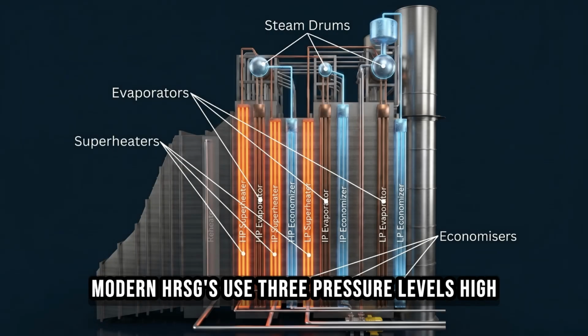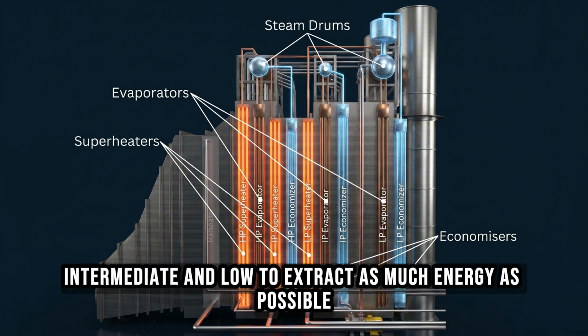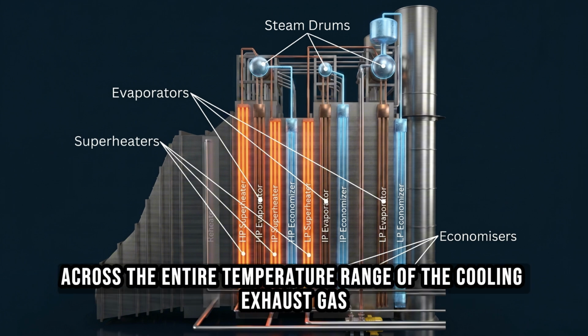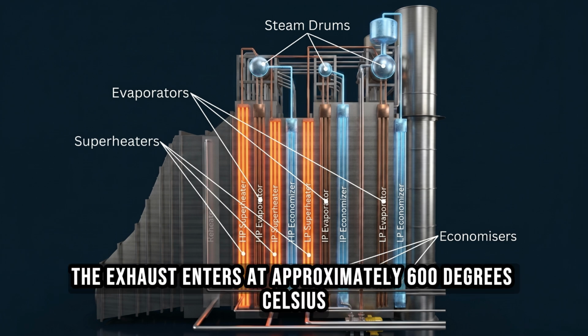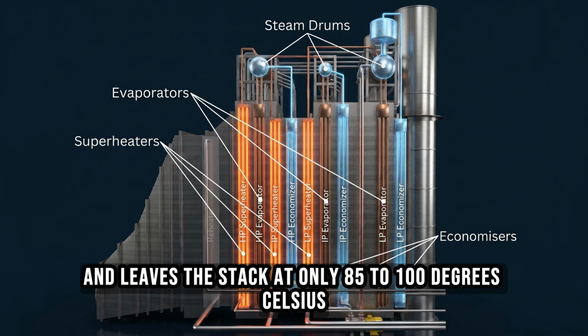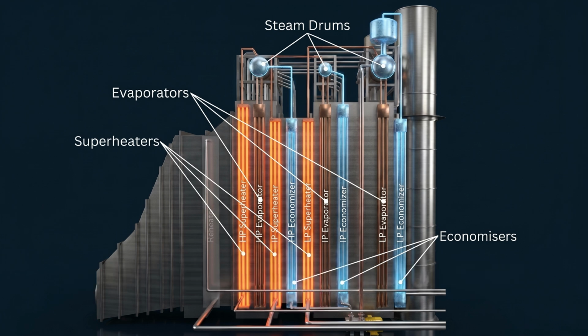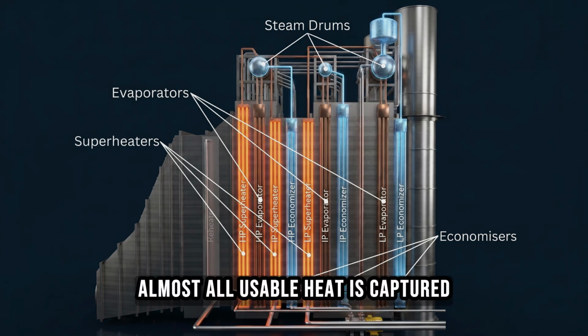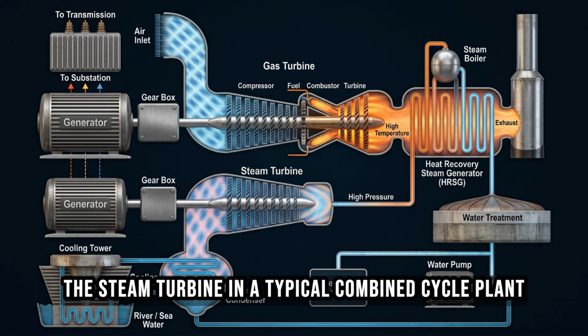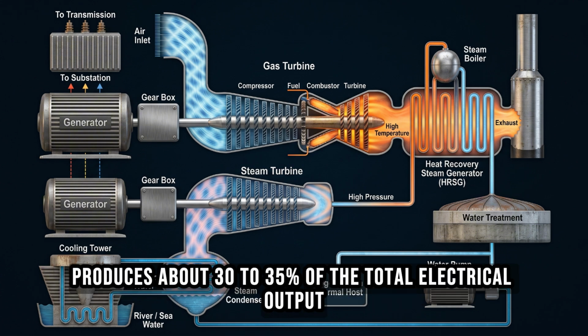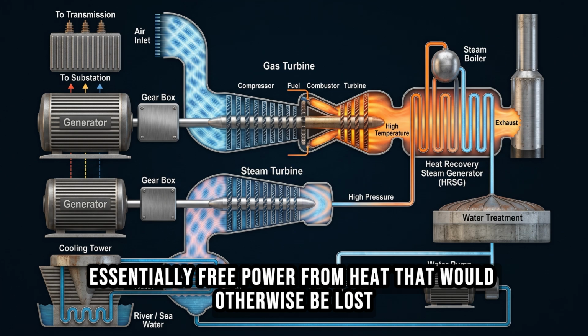Modern HRSGs use 3 pressure levels, high, intermediate, and low, to extract as much energy as possible across the entire temperature range of the cooling exhaust gas. The exhaust enters at approximately 600 degrees Celsius and leaves the stack at only 85 to 100 degrees Celsius. Almost all usable heat is captured. The steam turbine in a typical combined cycle plant produces about 30 to 35% of the total electrical output, essentially free power from heat that would otherwise be lost.